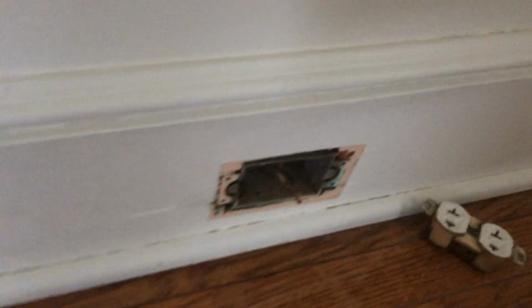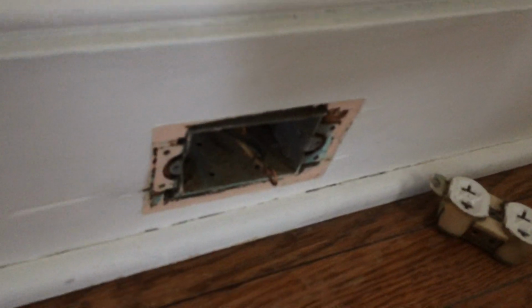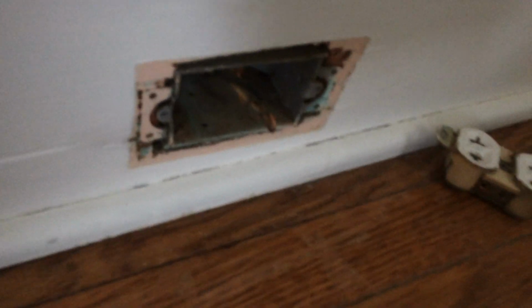And then we're taking a look, since we got the electric turned off, which it turns out you really need to test each outlet because there's 3 in this room. 2 went dead when we turned the light off, but the third one is still live, so that's hooked on a different line. So here we're pulling out the old receptacle, and in here you probably can't tell, but it turns out there is 3 wire.